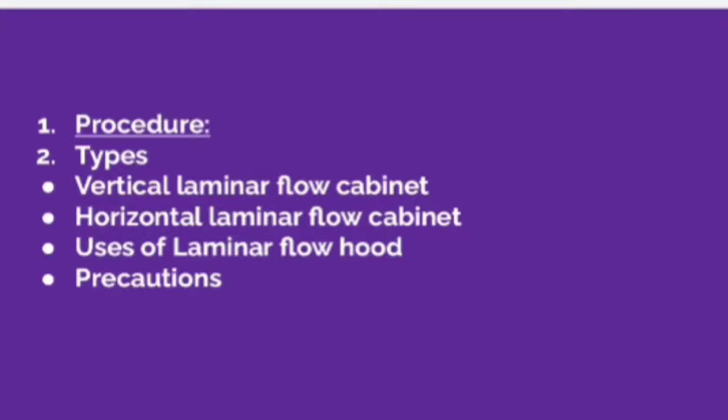Now, procedure for running the laminar airflow bench. The procedure to be followed while operating a laminar flow cabinet is as follows. Before running the laminar airflow cabinet, the cabinet should be checked to ensure that nothing susceptible to UV light or UV rays is present inside the cabinet.